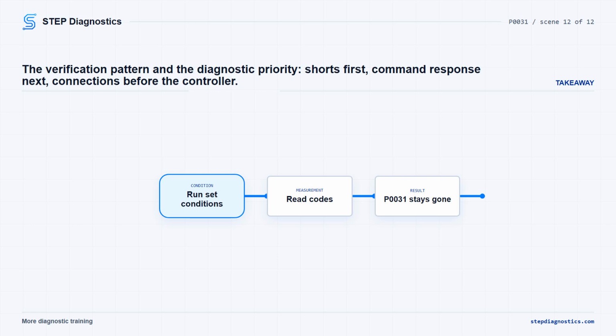The takeaway is simple. This is a low heater control circuit code, so prove the shorts first, prove the command response next, inspect the connections before blaming the controller, and do not overlook the sensor designation conflict in the actuator branch.